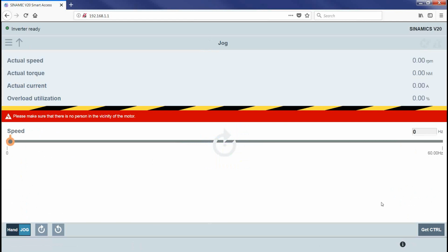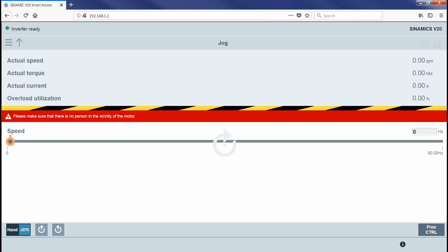So here's jog mode. I'm going to take control of the drive. This is the get control button. I'm going to say jog. I'm going to hold the jog button down. And it's going at 150 RPMs. You probably can't hear that, but I can hear on this end. All right, stop, go reverse. Notice actual speed is 0 because it's trying to make it run negative or in reverse. So that's jog.